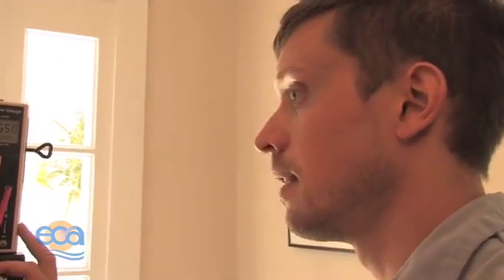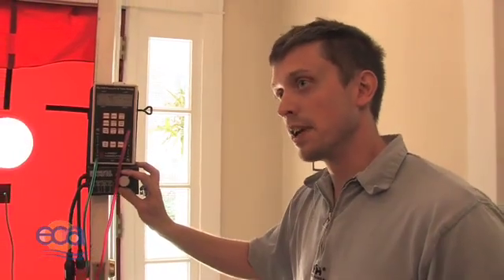You pressurize at 50 pascals, and we have an air movement of 3,550 cubic feet. I would say that's pretty good. How many square feet do you have, if you had to estimate? Probably under 2,500 — well, counting the basement, probably over 2,500, but I don't think it's 3,500. I'll get a more accurate measurement. I would say your home is pretty tight. I would expect the minimum air tightness to be something like 1,200. What do you typically see in a house, Chris? In Philadelphia, we typically see four to five times leakier than the standard.